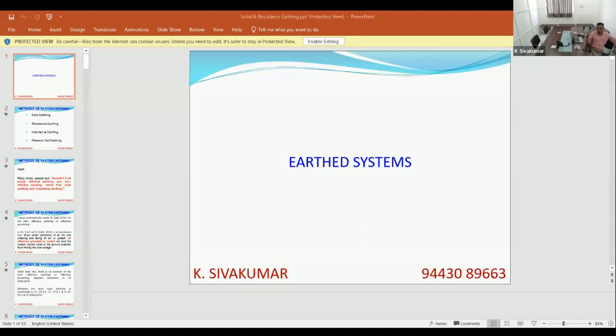Now we have to always design our system for the worst condition. If your zero sequence impedance is more than your positive sequence impedance, no question, the fault current will be lesser. But when I design my system, I have to design for the worst condition. So I assume that it is equal. When zero sequence impedance is equal or lesser, and you put the zero sequence impedance equal to the positive sequence impedance, Z1 plus Z2 plus Z0 becomes 3Z1.